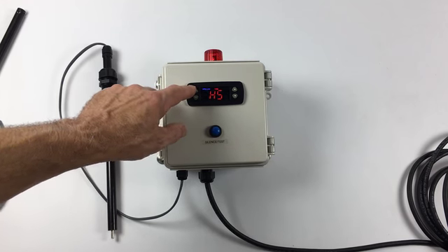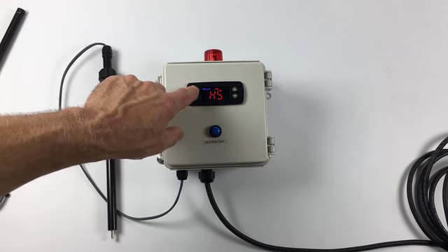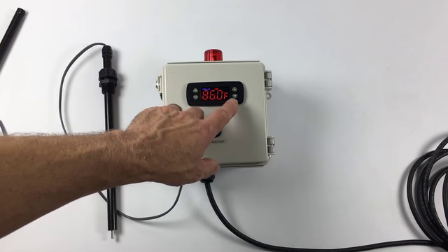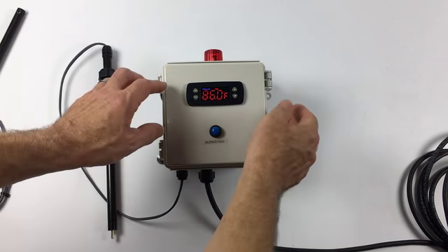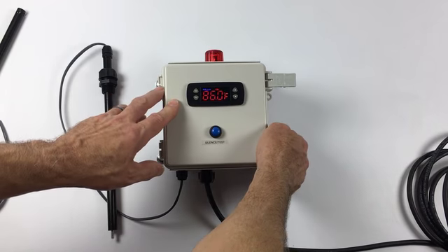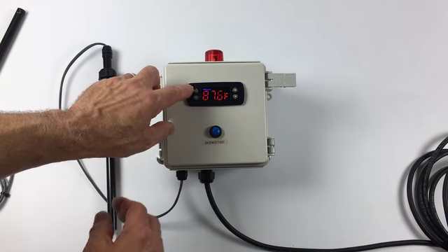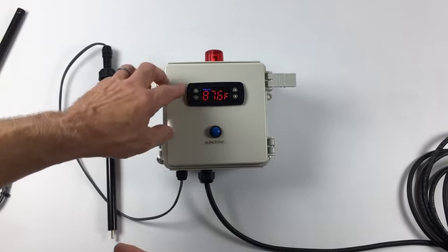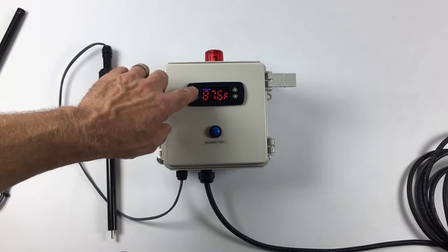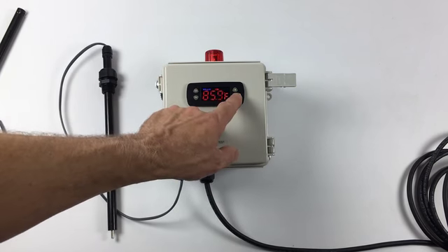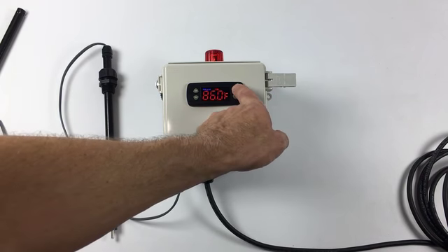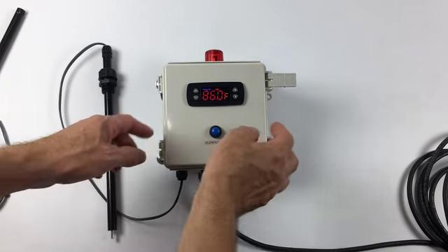This allows you to basically determine the maximum temperature that an operator can set it at. And right now I have it set for 86 degrees. So let me demonstrate. I'll go back to the normal mode. And now if I want to set the temperature, I can set it downwards, but because the maximum is 86, I cannot set it any higher than 86.